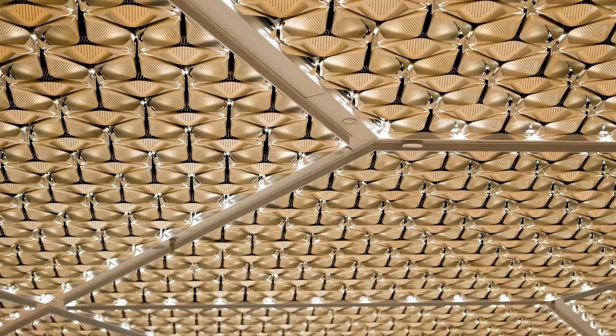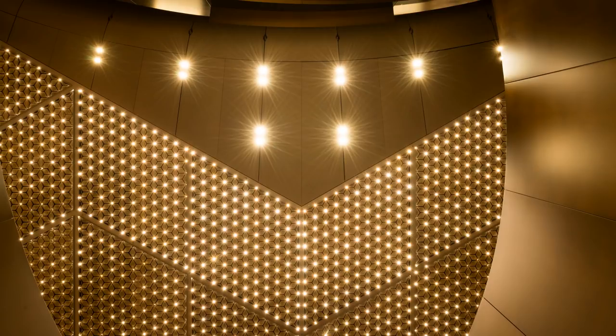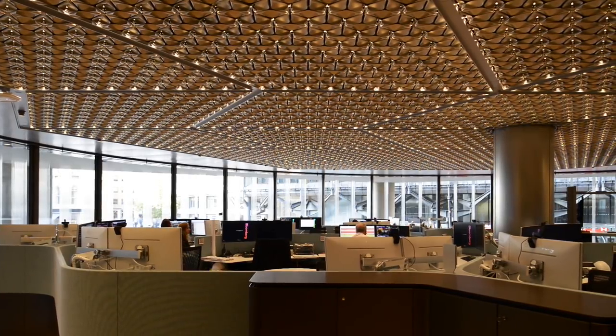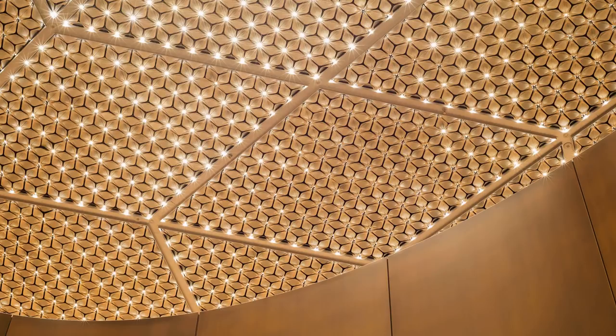The Bloomberg integrated ceiling panel combines acoustics, lighting and chilled water — it's a radiant cooled product. The petals increase the surface area and that is all within a hundred millimetre depth. The lighting is a key feature within the panel, providing a lux level of 300 lux. It gives superb uniformity because of the spread of LEDs across the space, and the metal petals also deliver very good acoustic absorption performance.